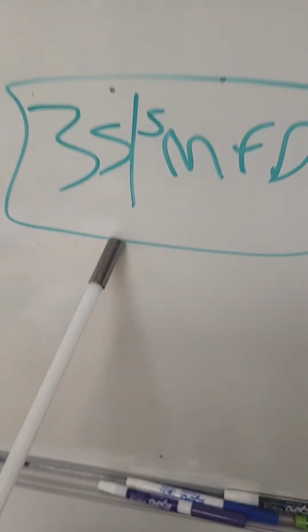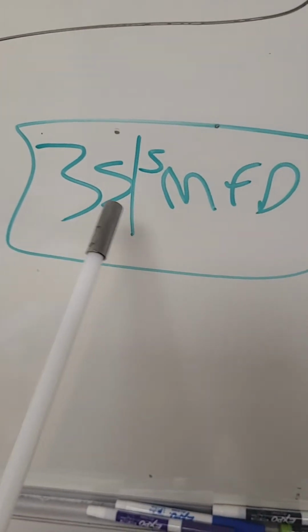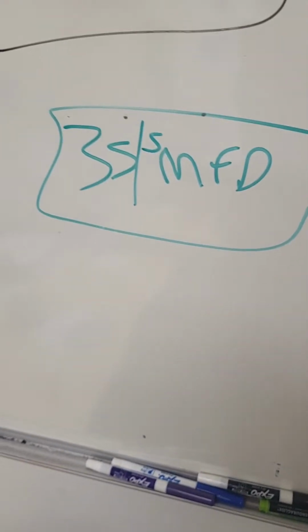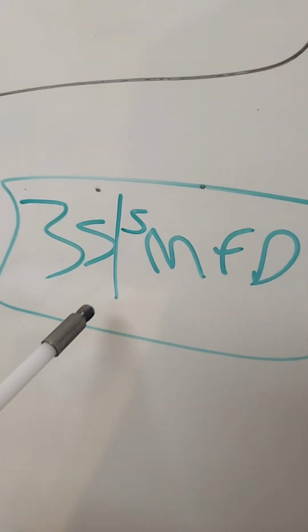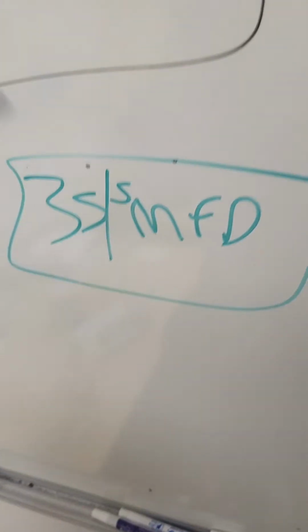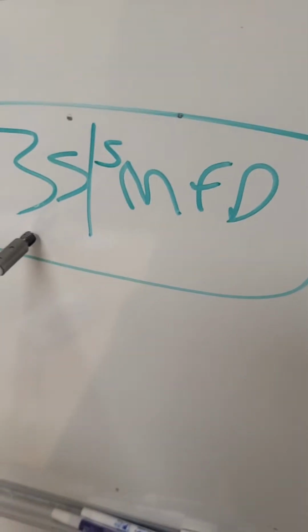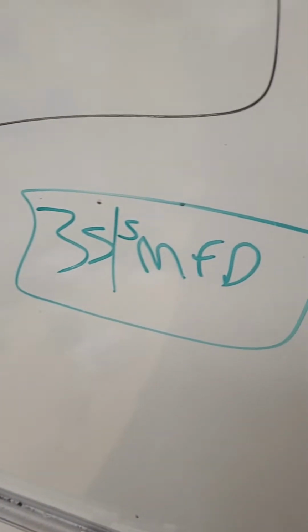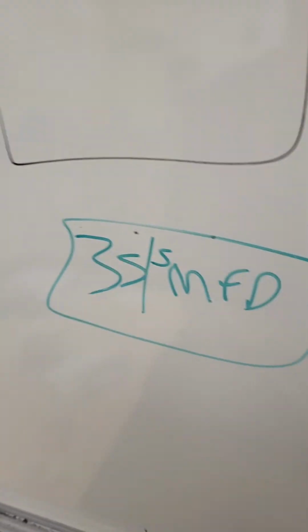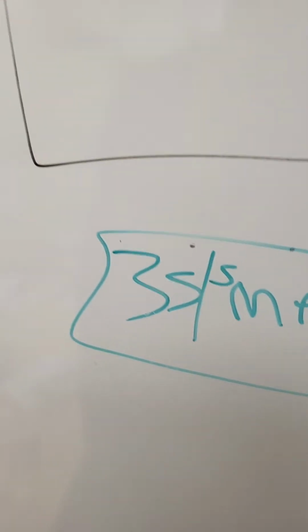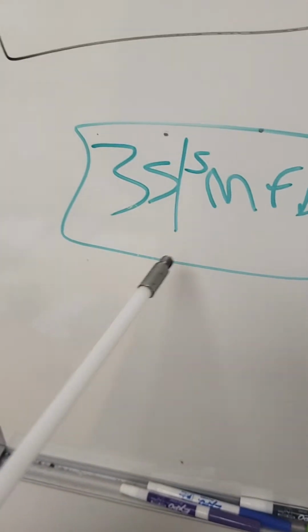If, hypothetically speaking, you have a 35/5 microfarad run cap and you didn't know what the system was rated for - and I say this generously, because most of the time you should know what the system is rated for, either from the data info on the old cap, or, as I mentioned in previous shorts, you should know how to find info on the current system to figure out what size cap it's rated for. You should know how to find that info.